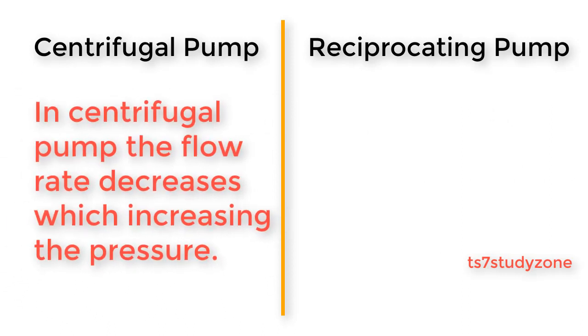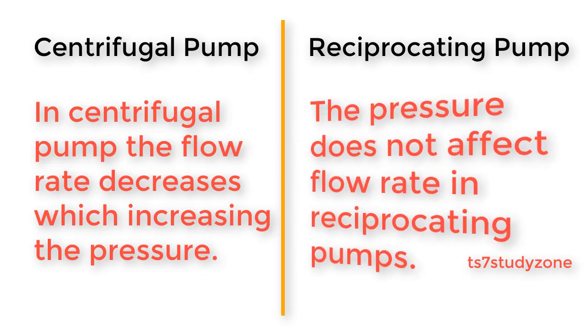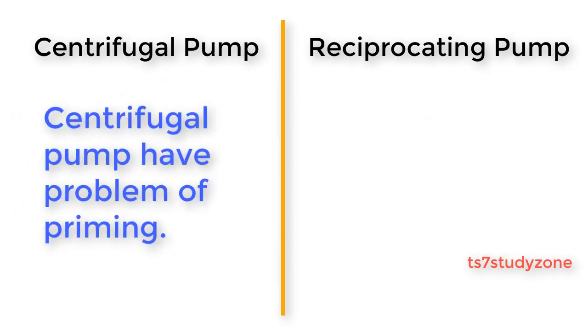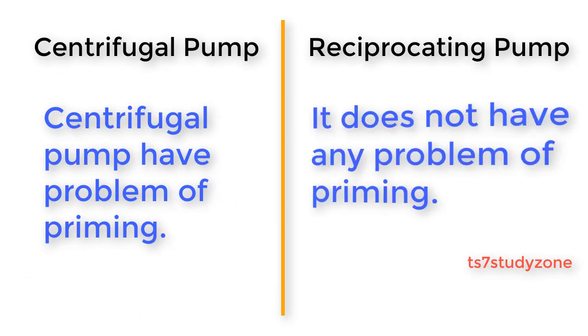In centrifugal pumps, the flow rate decreases with increasing pressure. In reciprocating pumps, pressure does not affect the flow rate. Centrifugal pumps have a problem of priming, while reciprocating pumps do not have any problem of priming.